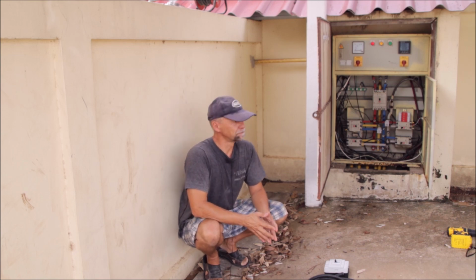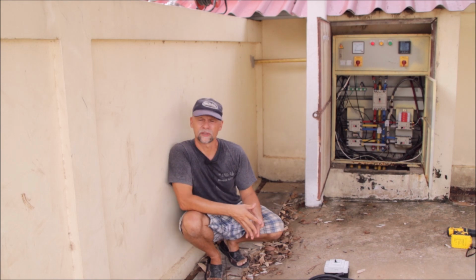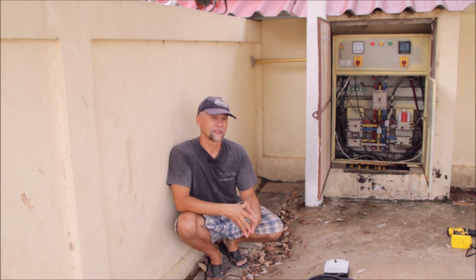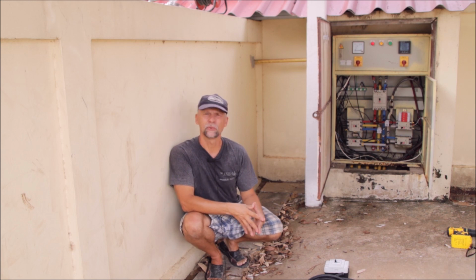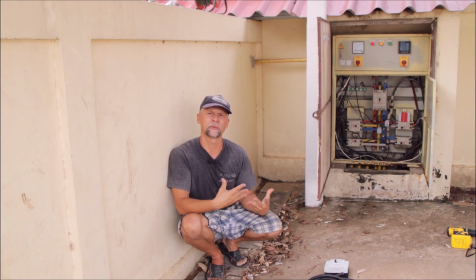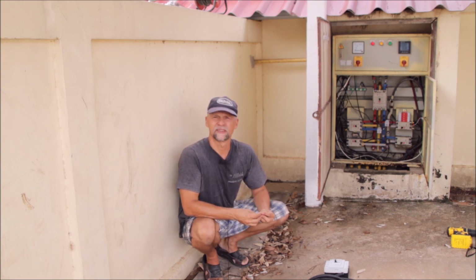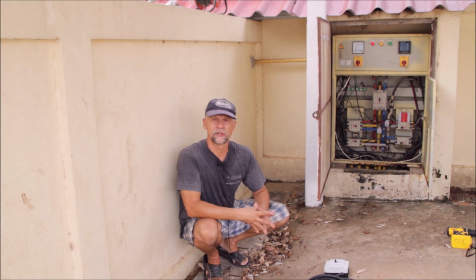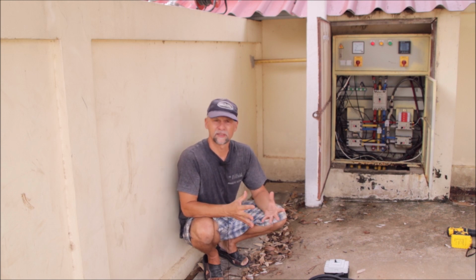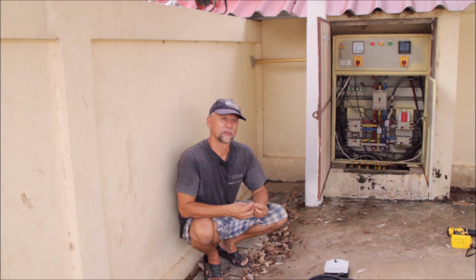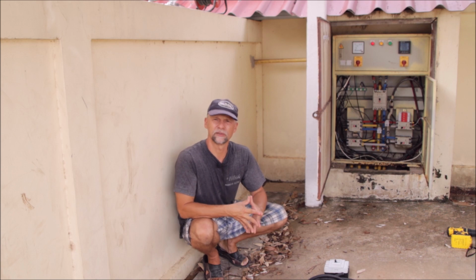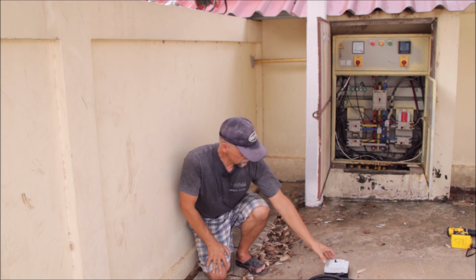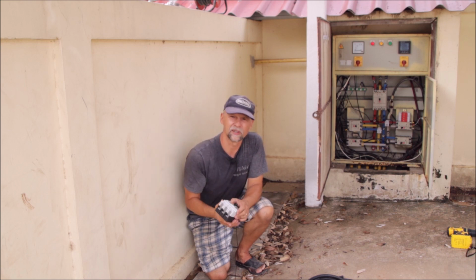That sounds quite okay. But if you look up how these breakers work, you will find in their data sheet that typically you need around 3 times the nominal current to make such a breaker trip quite instantly. So we need 300 amps minimum to trip this breaker safely, and 550 is quite a good value over those 300. So we could be sure the current condition would work quite well. But still, I want to change it to an 80 amp instead of the 100.